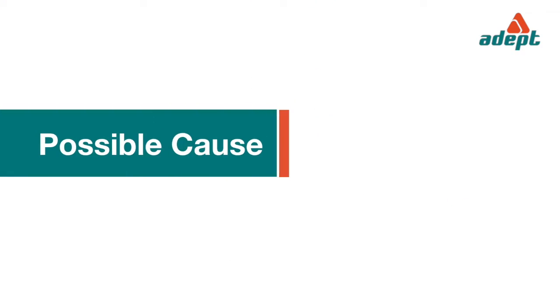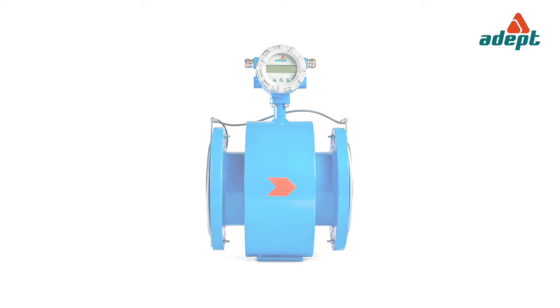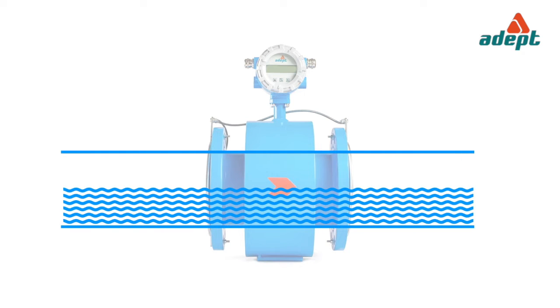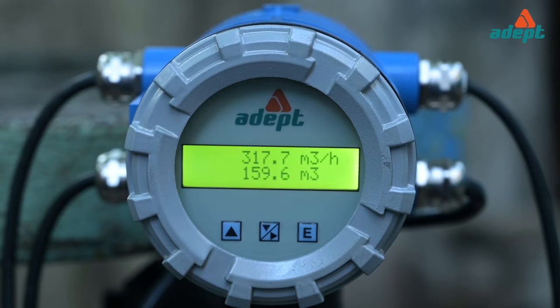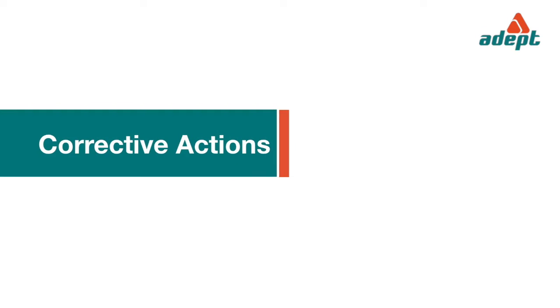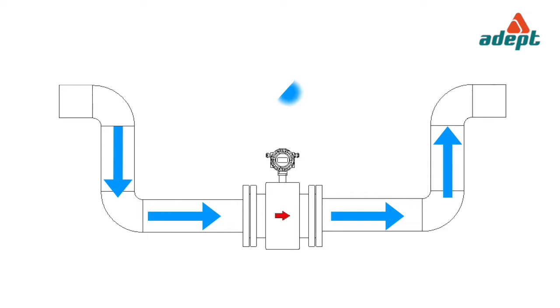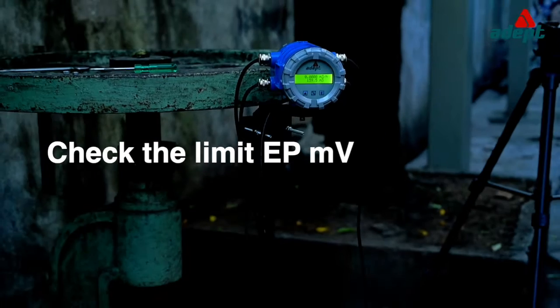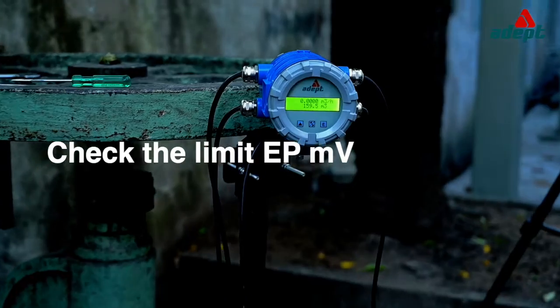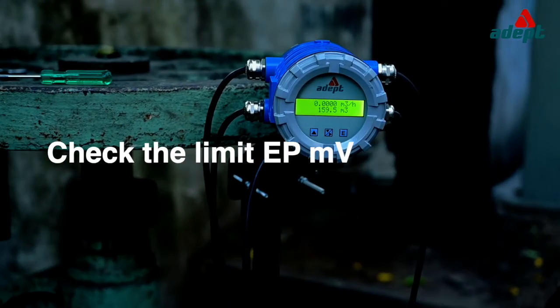Empty pipe indicated. Possible causes: flow tube is not full, or the empty pipe limit is set to a low value. Corrective action: confirm installation is correct and that the flow tube is full, then check. Check the limit EP MV.